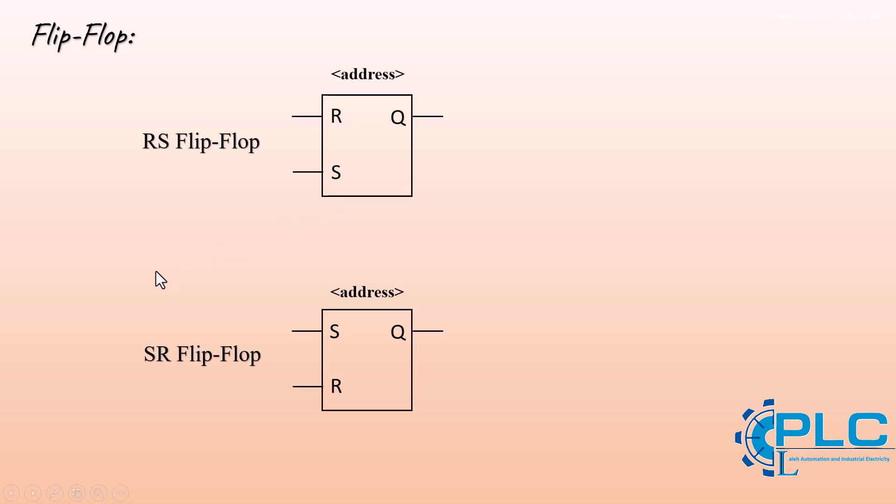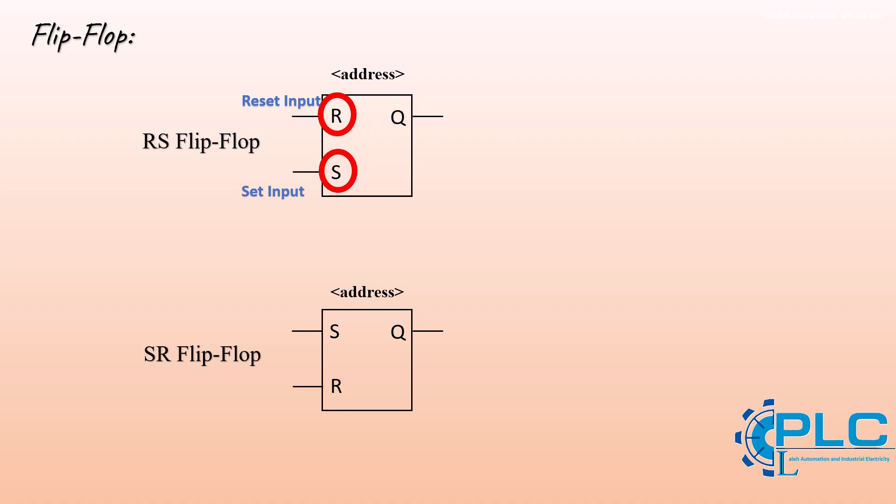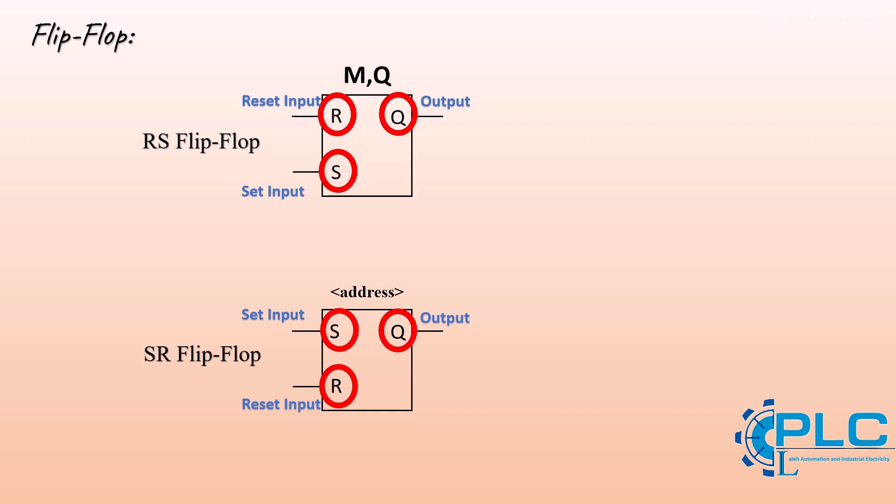Let's start with the RS flip-flop. Both flip-flop instructions have two main inputs. The first input is labeled R, which stands for reset. The second input is labeled S, which stands for set. We also need to define an address for the flip-flop that stores the condition of whether the flip-flop is active or inactive. This can be either a memory bit M or a physical output Q, depending on the needs of your program. The flip-flop block also has one output. You can use this output in your program logic or leave it unused if it's not needed directly.